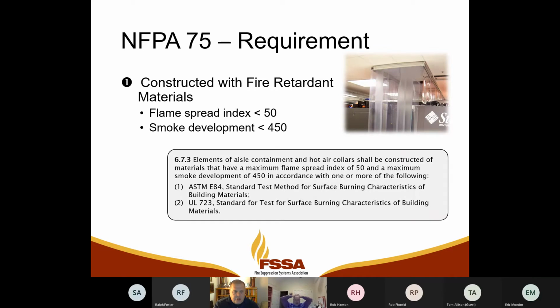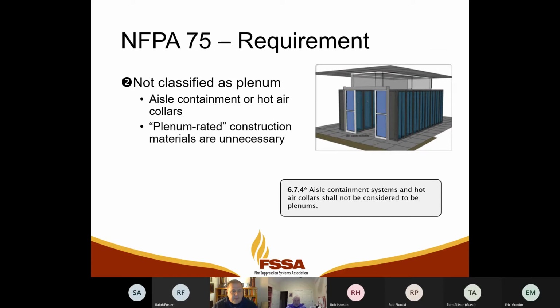Since they're not plenums, but they're in this sort of plenum environment, the requirement is that they need to have a flame spread index of less than 50 and smoke development index of less than 450. So it's not as strict as plenum rated materials, but there is a requirement there now. So there's something for containment system manufacturers to now make sure that their products meet inside of the fire codes.